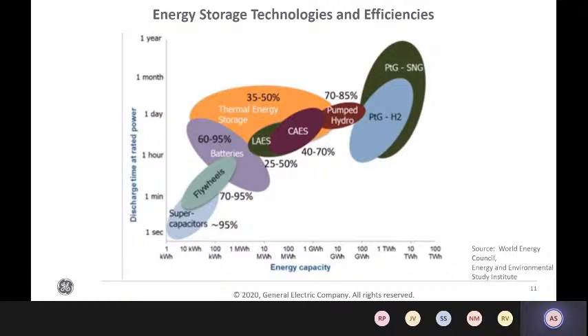Another technology is called CAES, compressed air energy storage. In this technology, electricity is used to compress air, and energy is recovered again when the compressed air is expanded into a turbine. When the air is compressed, it also heats up, so if the air stored in a vessel loses this heat over time, the round-trip efficiency will be lower. This is especially a problem for longer-term storage. That's the situation with CAES technology, compressed air storage.